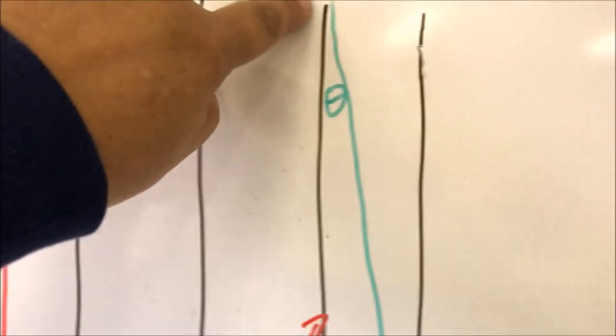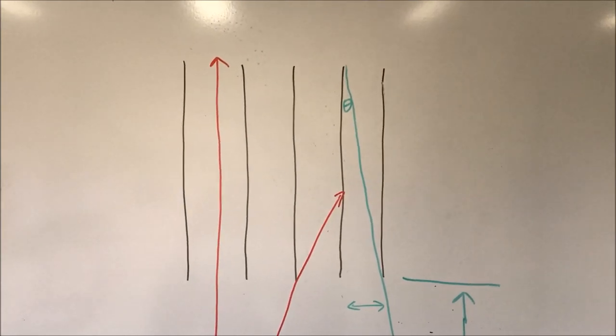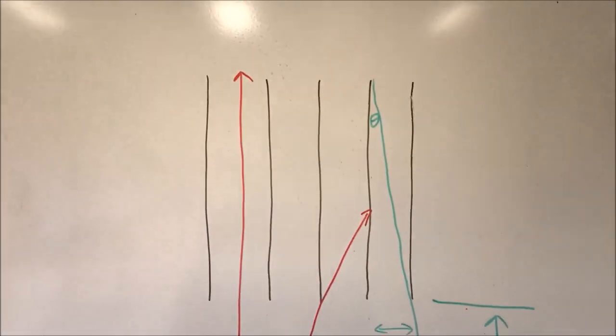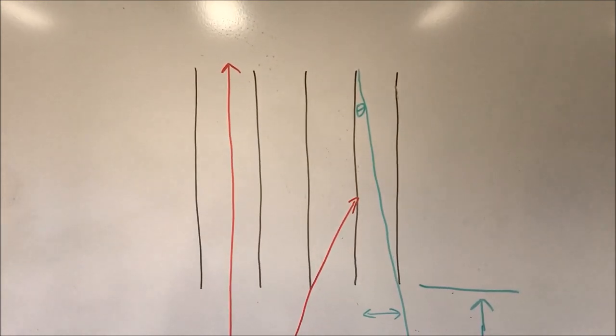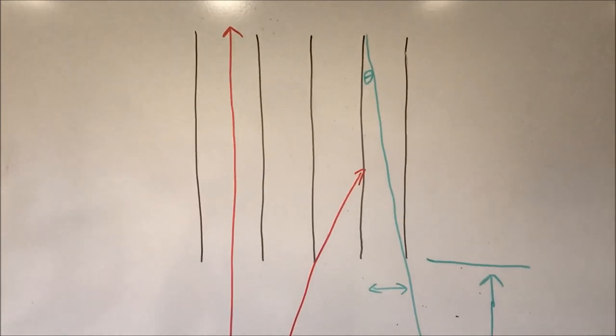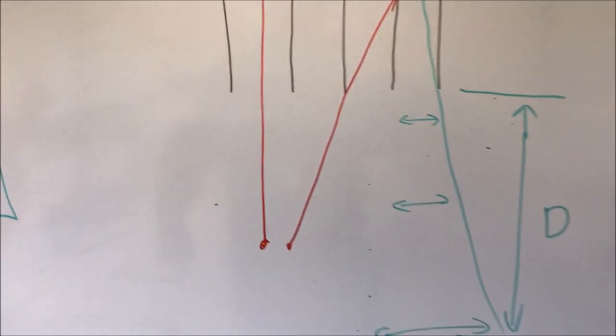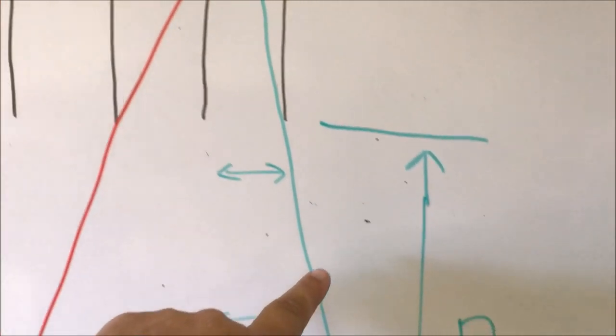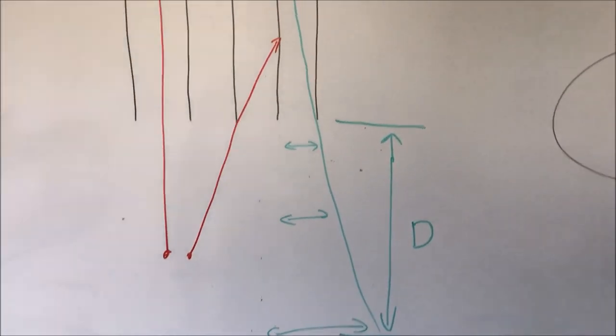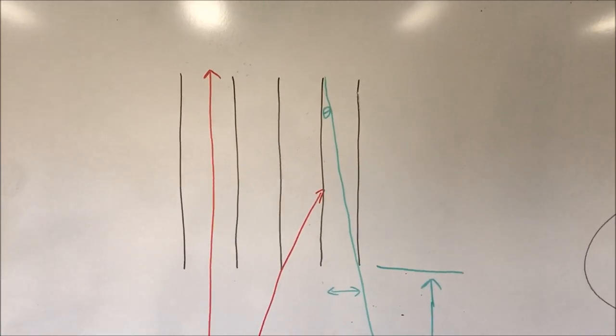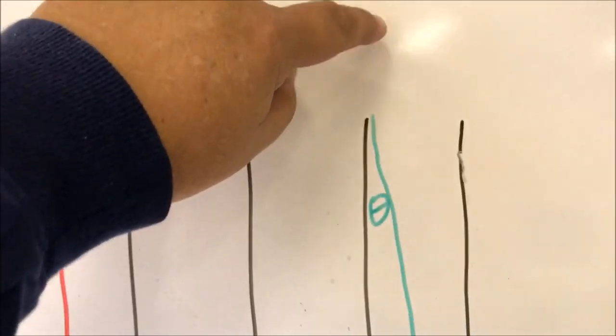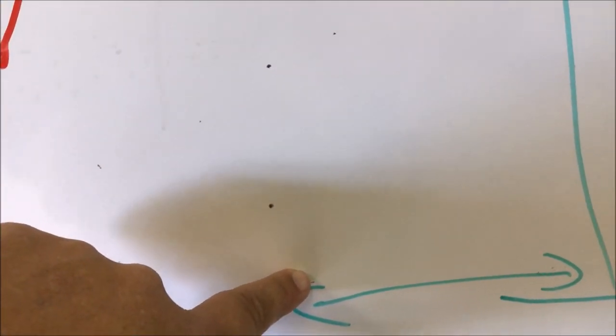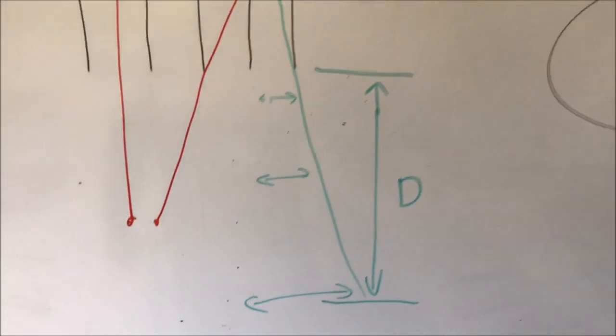This brings us to resolution. We have this angle theta, defined by the line drawn from the two ends of a single hole. That represents the angle a photon could come from without being rejected from data collection. If we extend that down — imagining the patient is at the far end — the further the patient or object of interest is from the detector, the bigger that angle, resulting in a localization error. This impacts resolution, and that's actually going to be experiment one if you look at the other YouTube clips.